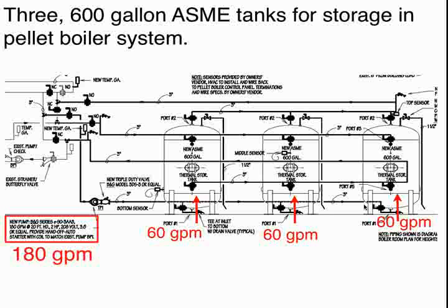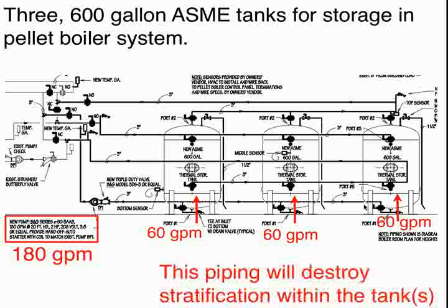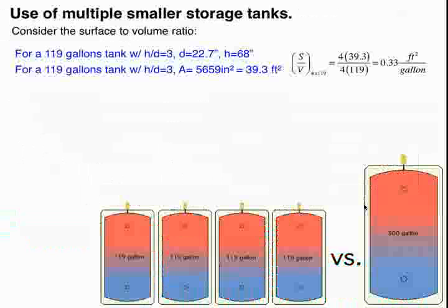Now, these are 600-gallon tanks. They're roughly about 6 or 6.5 feet tall. Imagine a 60-gallon per minute flow straight up into a container that's 6 feet tall. You're going to get a strong mixing component. So fortunately, this was caught at the design phase, and these tanks have been modified before. They're actually fabricated. And the interesting thing here, there's 3 different flow inlet diffuser designs that are being used, and ultimately those will be studied to see which of those inlet diffuser designs is most effective in helping preserve stratification. So again, be careful of vertical flow jets.